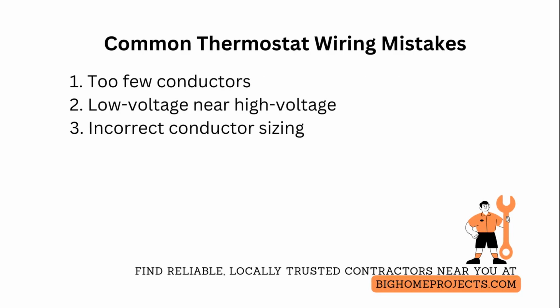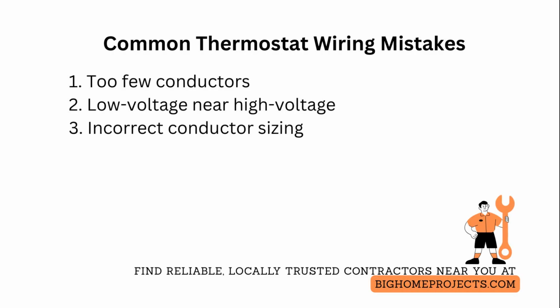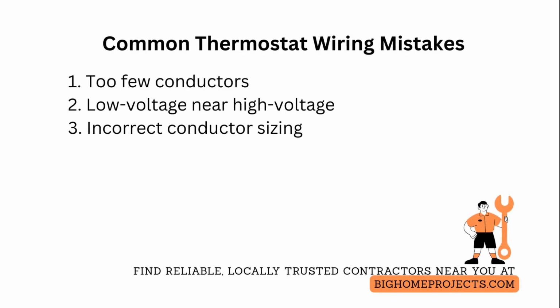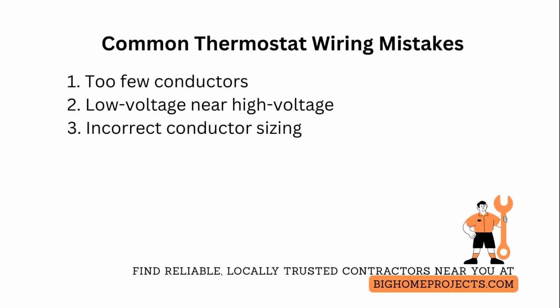One of the top 3 thermostat wiring mistakes is using too few conductors, which leads to missing common or fan wires and causes smart thermostat power issues. Fix this by always choosing 6-conductor cable and testing the control board for an available common terminal before purchase.